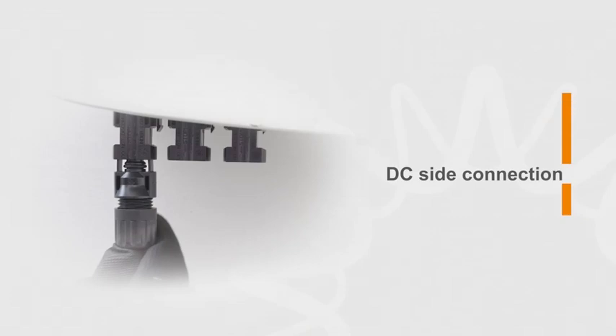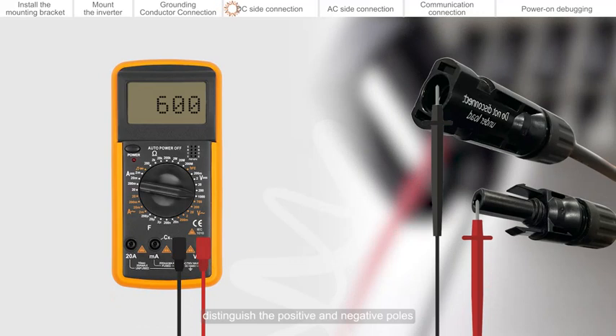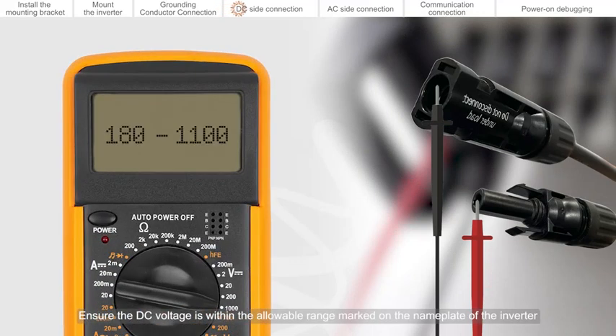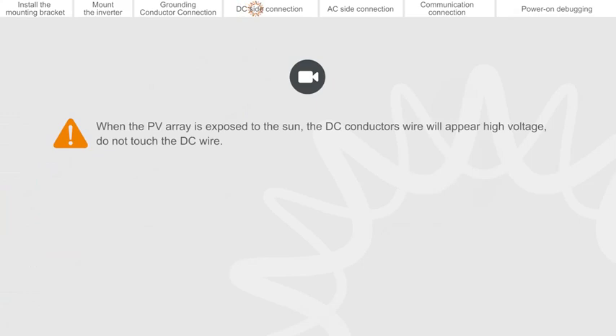DC side connection. Please use a multimeter to measure the open circuit voltage of the PV strings. Distinguish the positive and negative poles. Ensure the DC voltage is within the allowable range marked on the nameplate of the inverter. Please refer to the SOLIS demonstration video for how to make a DC connection cable. When the PV array is exposed to the sun, the DC conductor wire will carry high voltage. Do not touch the DC wire.